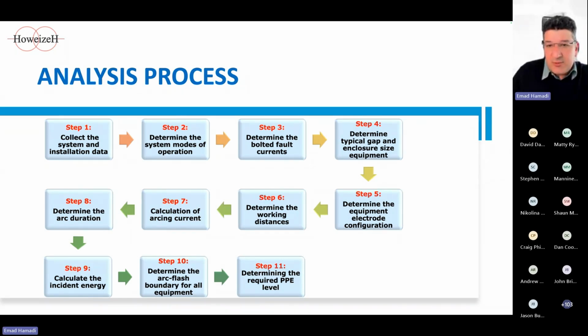The process is normally done in 11 steps. These steps are based on IEEE 1584. We start with gathering the critical data that forms the backbone of the analysis and enables us to understand the dynamics of the electrical system. Following this, we use precise calculations to determine the energy level associated with the arc flash incident and the safe boundary within which personnel can operate.